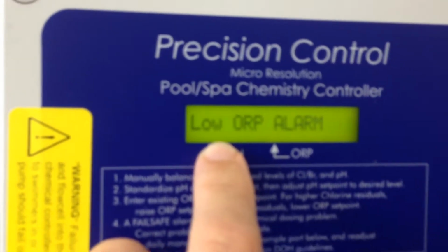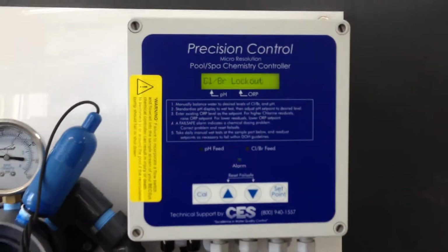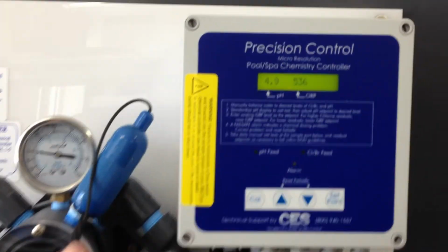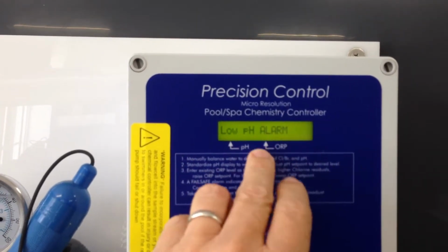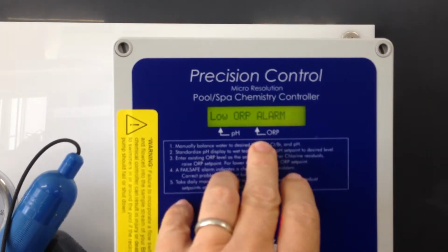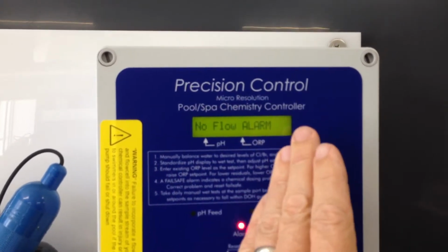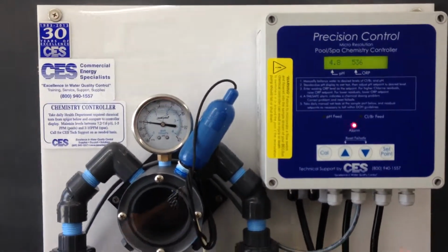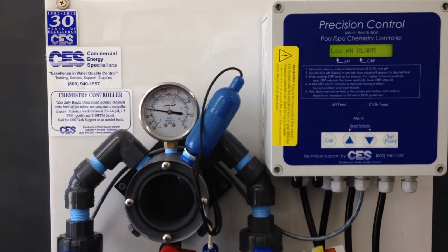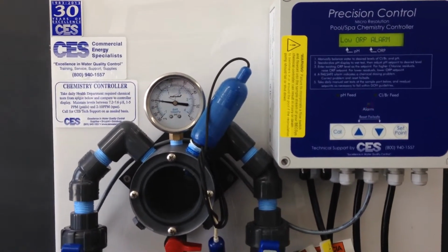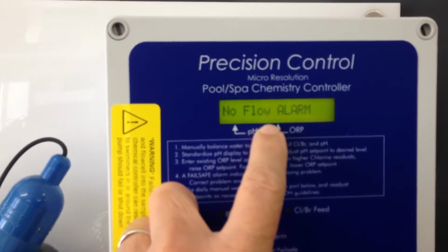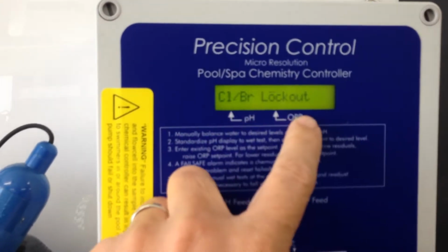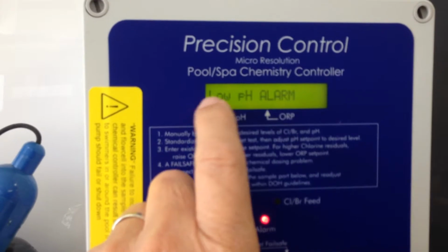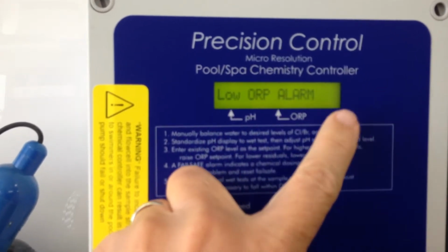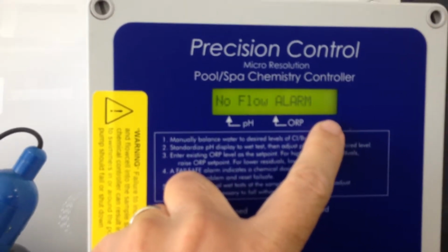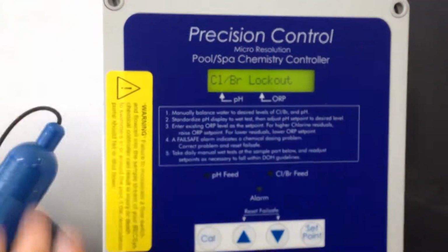And then a couple of important things, which Mike will go over when he's there: if the pH is too high, chlorine is not worth as much as it used to be. So if it's above 7.8, you can get a condition where this controller will continue to pump in chlorine and cause an unsafe condition in the pool. So we have it set up so if it goes above 7.8, it locks it out. It locks out on both low pH and high pH, and the reason is because the chlorine values have changed with the ORP.